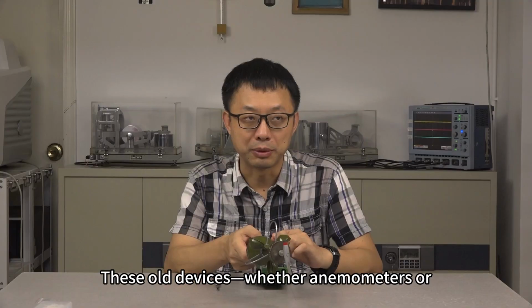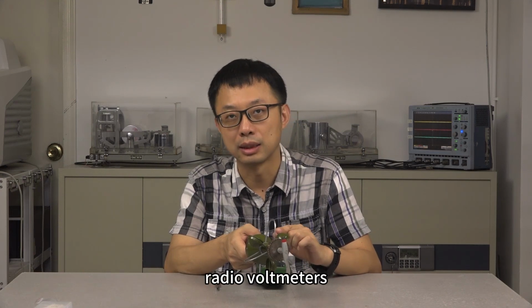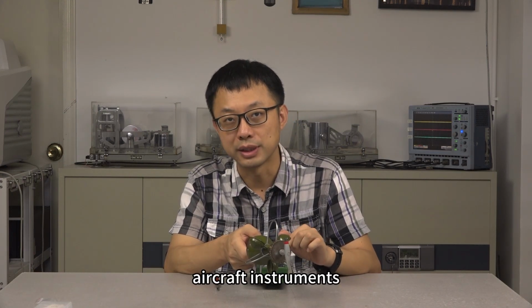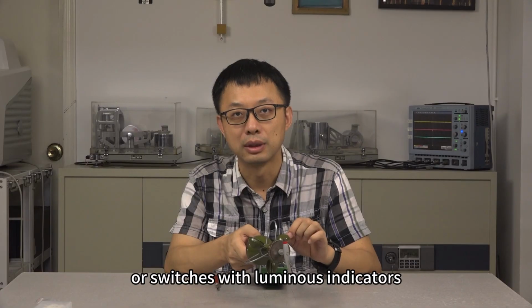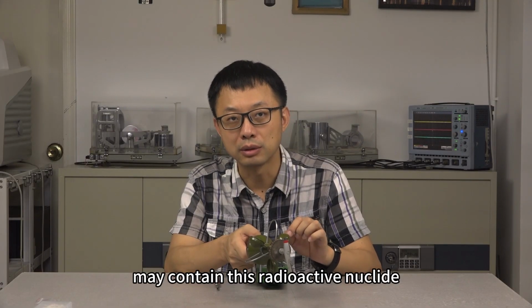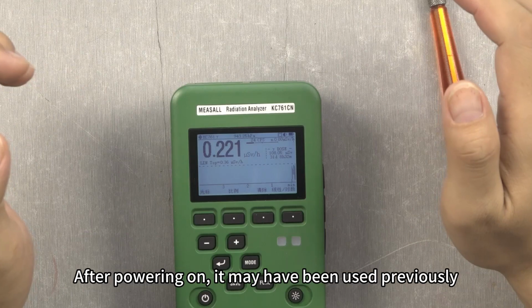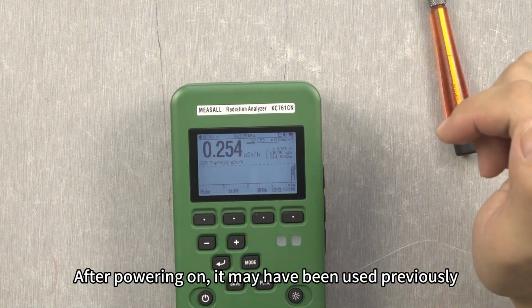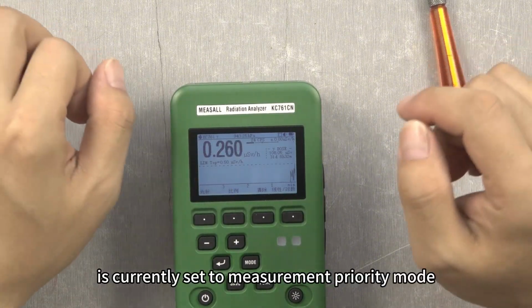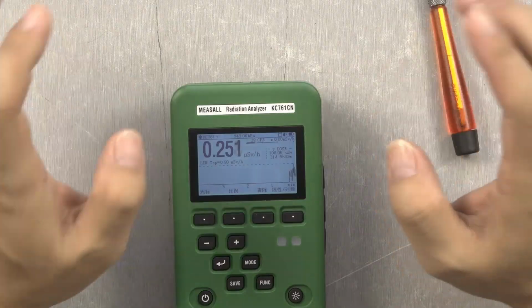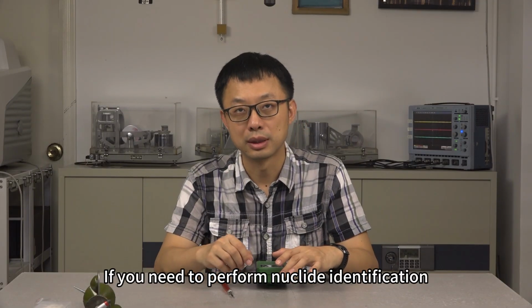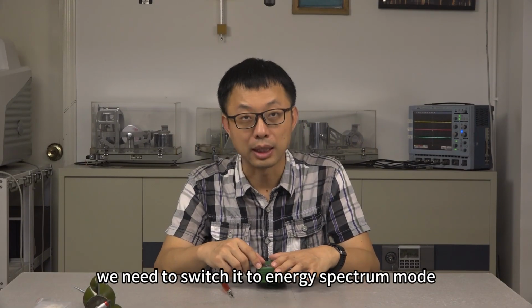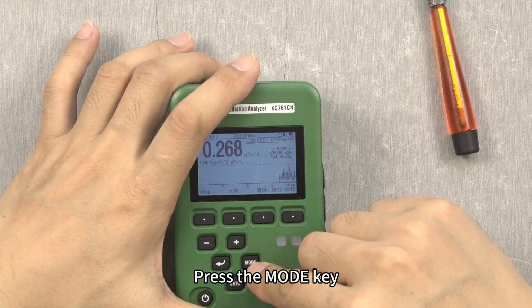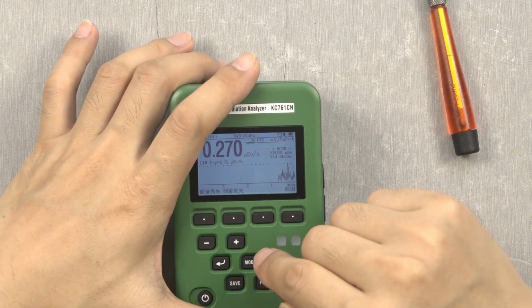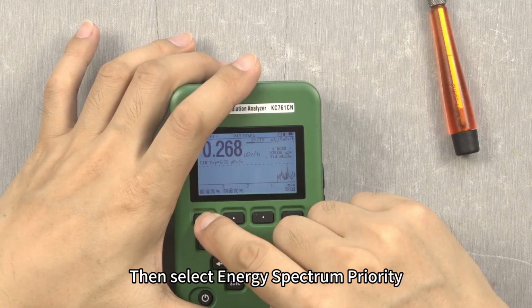These old devices, whether anemometers or radio voltmeters, aircraft instruments, with switches with luminous indicators, may contain this radioactive nuclide. After powering on, it may have been used previously. This instrument is currently set to measurement priority mode. If you need to perform nuclide identification, we need to switch it to energy spectrum mode. Press the mode key. Then select energy spectrum priority.